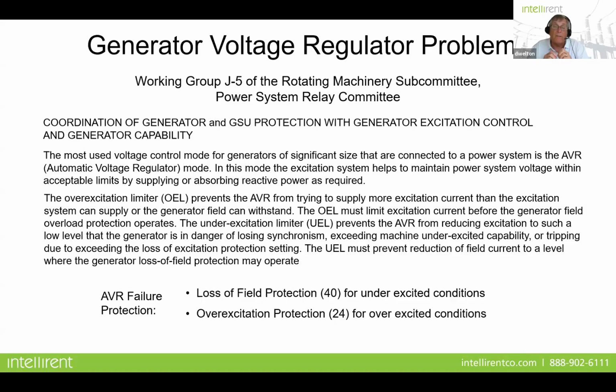Now, there's an overexcitation limiter in most large generators that prevents the AVR from trying to supply more excitation current than the excitation system can supply. But these systems can fail. I mean, one of the definitions of what protective relays do is that they're there when systems fail. And this is one of the things that happens. Because remember, whatever happens with the generator that's directly connected to the transformer is also happening to the transformer. So if you have a volts per hertz condition or overexcitation in the generator, it's also going to create a problem for the transformer as well.